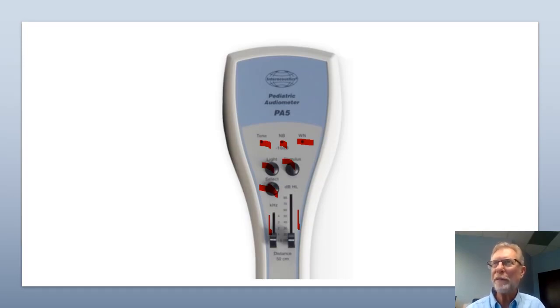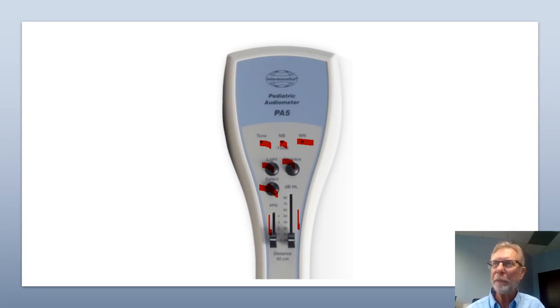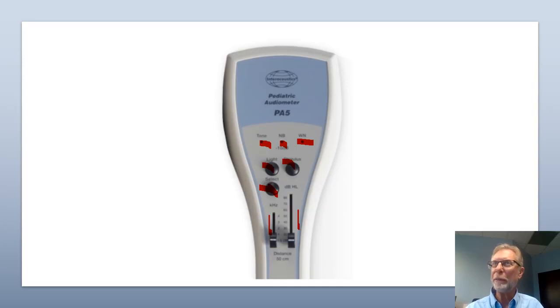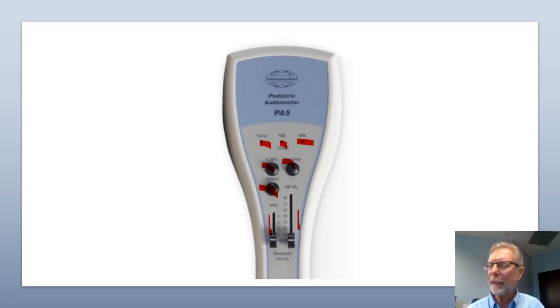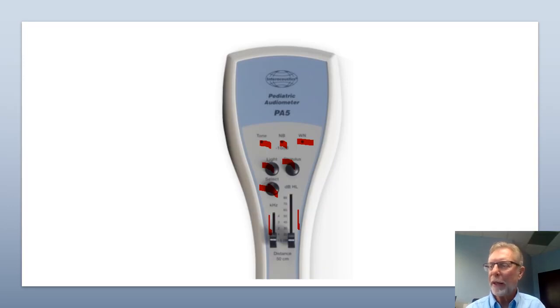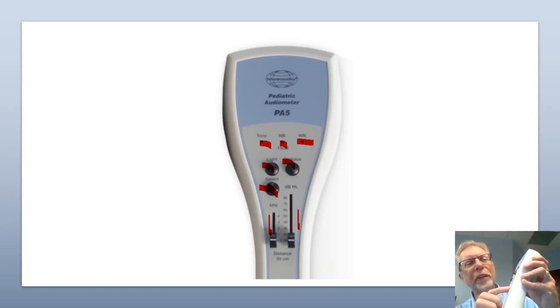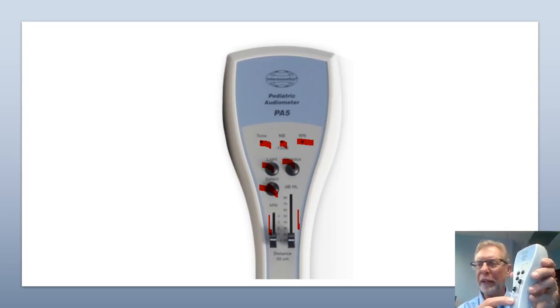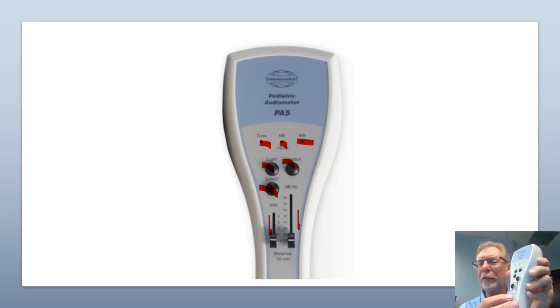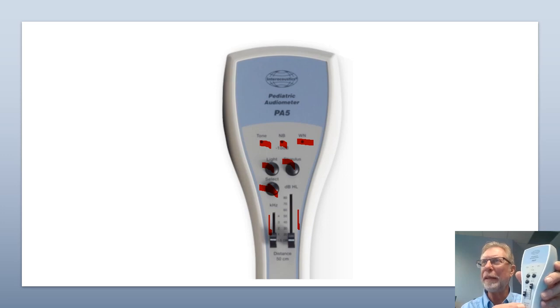If you have a sound level meter app on your phone, which I do, you can actually measure the intensity of the output. And you would typically do that at a loud level like 70 and you would see how far you had to be to be 70. And the owner's manual is in there. You can always refer to that. And that will indicate the distance, too. So I hope that has helped. In fact, the system, the unit actually says distance on it and it says 50 centimeters, which is about 18 inches.